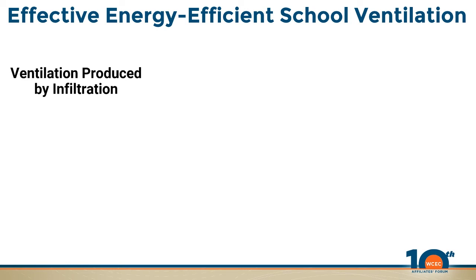At the one school we saw, control systems aren't set consistently, so at times the fan isn't even running when it needs to be. Another reason is that ventilation systems aren't commissioned correctly, so damper settings aren't correct, or in some cases not even hooked up. We actually encountered ventilation systems where they just skipped that part of the installation. That's rare, but we did see it.